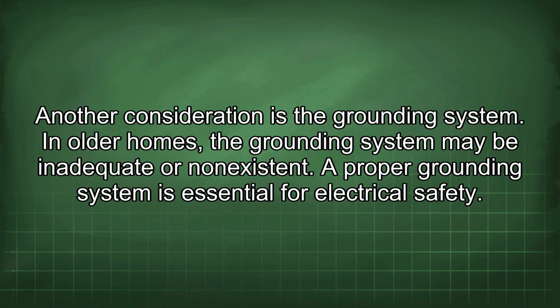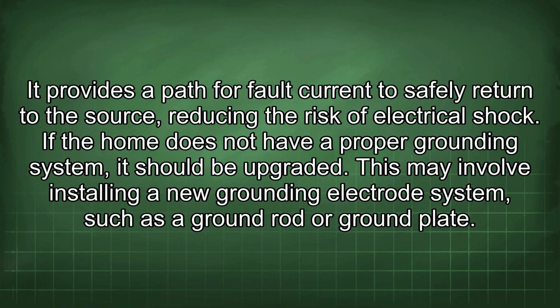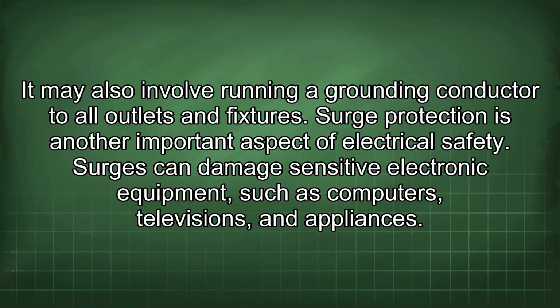Another consideration is the grounding system. In older homes, the grounding system may be inadequate or non-existent. A proper grounding system is essential for electrical safety. It provides a path for fault current to safely return to the source, reducing the risk of electrical shock. If the home does not have a proper grounding system, it should be upgraded. This may involve installing a new grounding electrode system, such as a ground rod or ground plate. It may also involve running a grounding conductor to all outlets and fixtures.